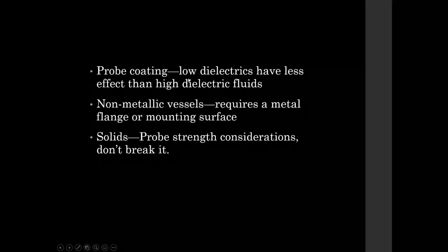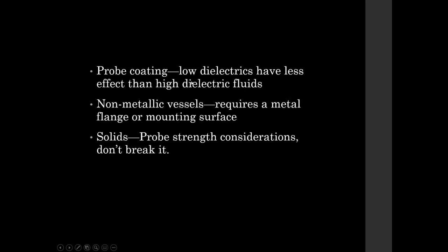Okay, probe coating, non-metallic vessels and solids, no diagrams here. But probe coating basically is when stuff gets built up on the probe, and again, some manufacturers will tell you this is not an issue. It may or may not be an issue. What usually determines that is the dielectric of that coating. Low dielectrics will have less of an effect. Higher dielectrics will have more of an effect when it comes to coating.